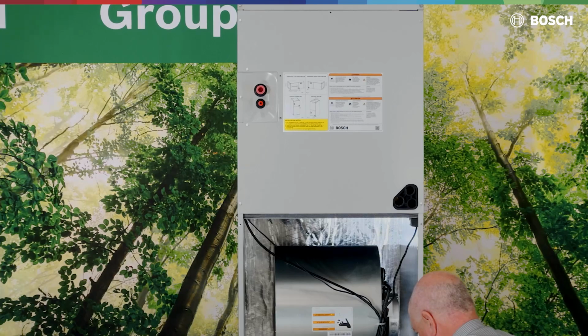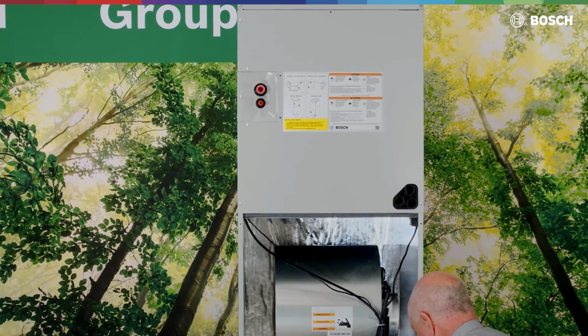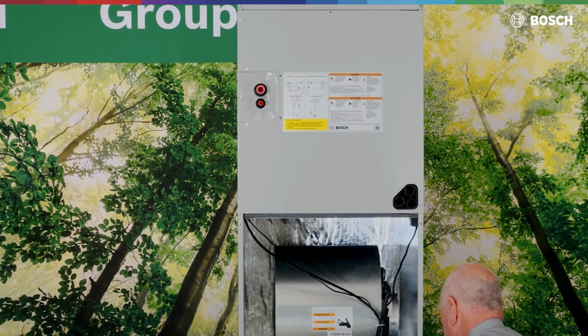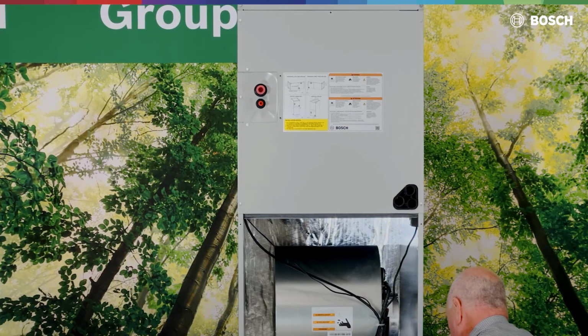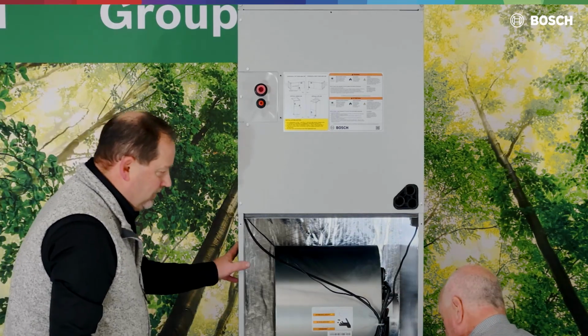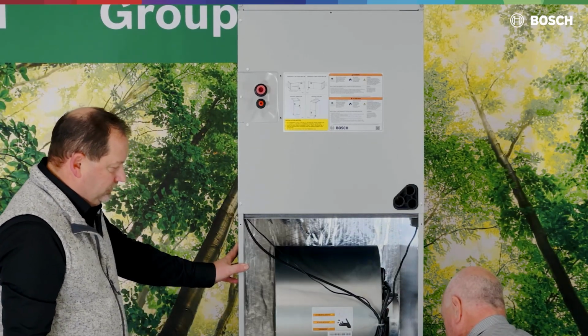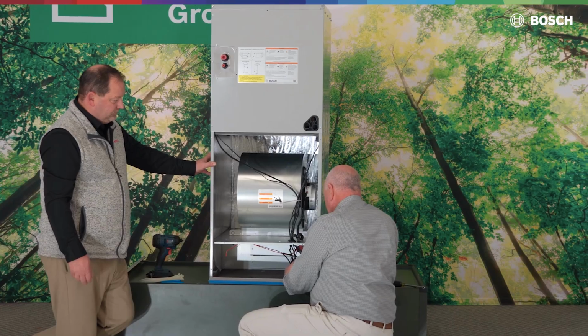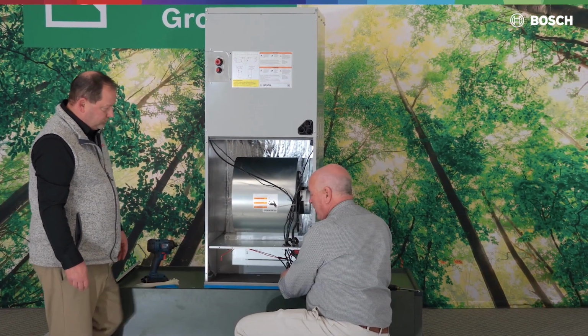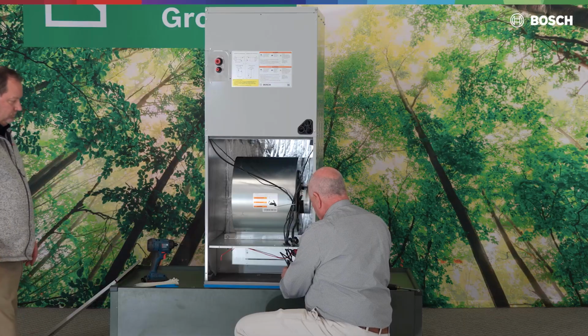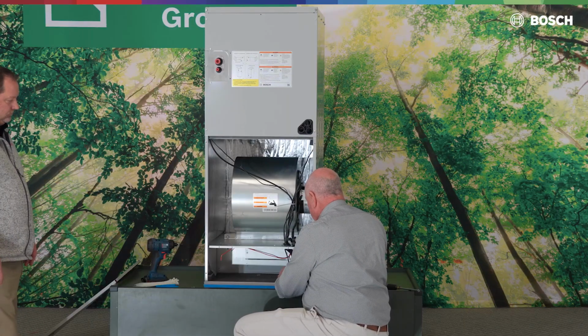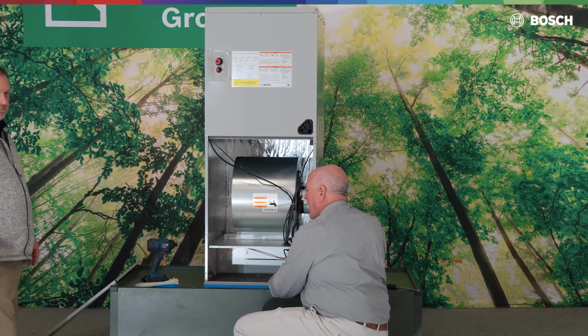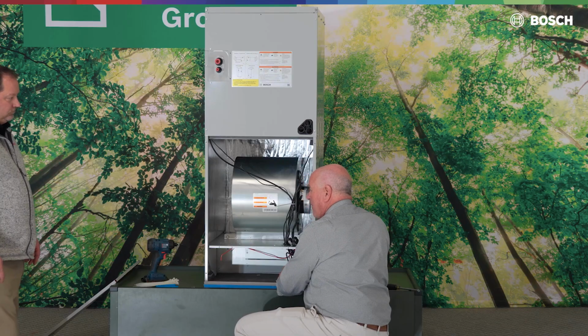Now I noticed, Dave, this doesn't have any heat strips in it. It doesn't. What do we do about that? Are there heat strips available? There are heat strips available. And guys and gals, it's up to your location. If you get to a situation where the temperatures can go below 13 below zero, you might want to look at having a form of backup, because these units can lock out when it gets to 13 below. It'll finish the call, even at minus 20, but when that call is satisfied, the unit will not start back up until we get above minus 13.